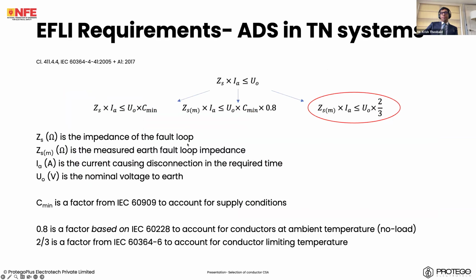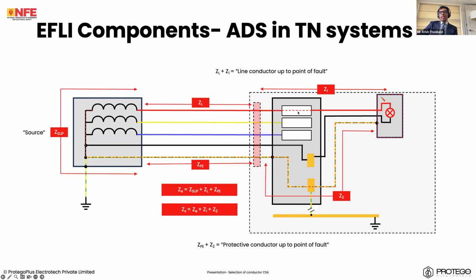What does this mean? The current causing disconnection in the required time, times the loop impedance, shall be less than or equal to the nominal voltage. You know this. There are a variety of safety factors taken into consideration across the world. In India, we consider two-thirds. I'll give you an example calculation. For instance, assume that this breaker is a B6 breaker, which means it requires 6 into 5, which is 30 amperes to disconnect instantaneously.